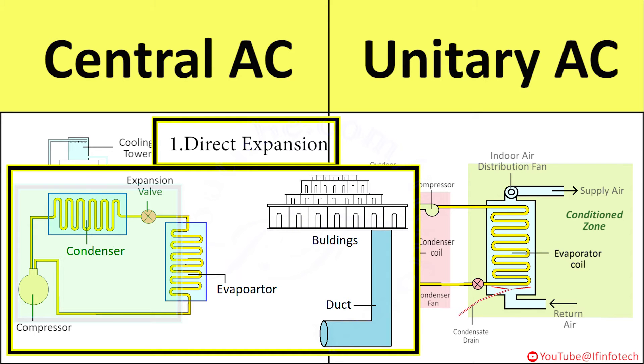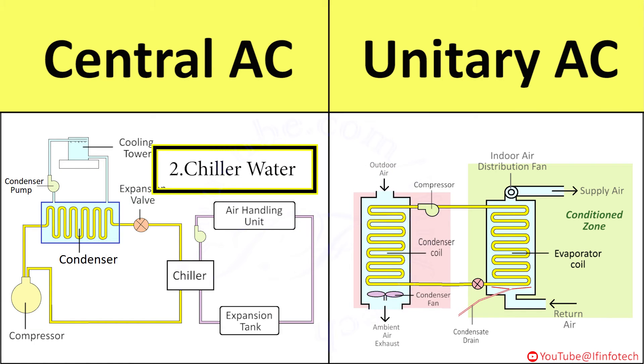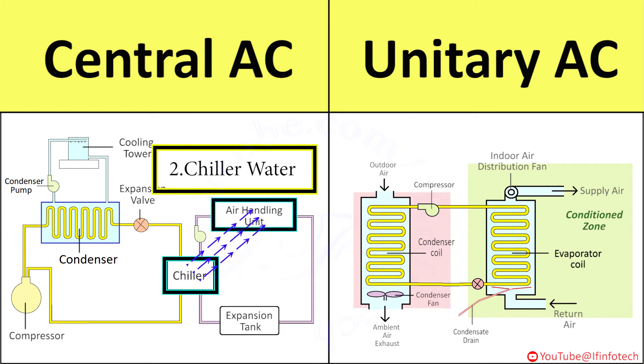The cooling coil of the refrigeration plant is fixed in the air handling unit and the expansion valve is provided very close to the cooling coil. In the chilled water system, chilled water or brine solution is circulated through the cooling coil in the air handling unit to cool the room air. The chiller in the chiller package and the cooling coil in the air handling unit are connected by chilled water pipes or brine pipes to pump and circulate it between the chiller and cooling coil.